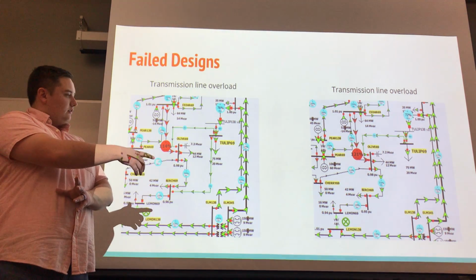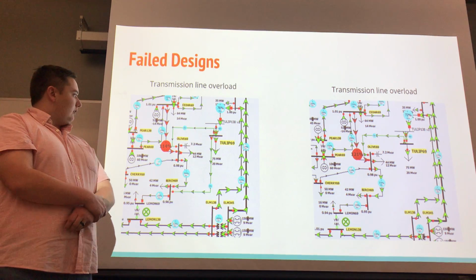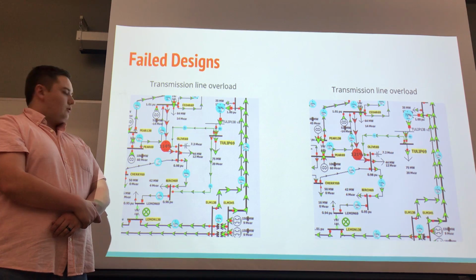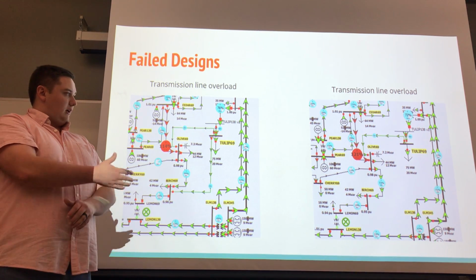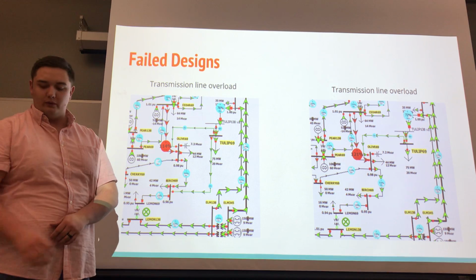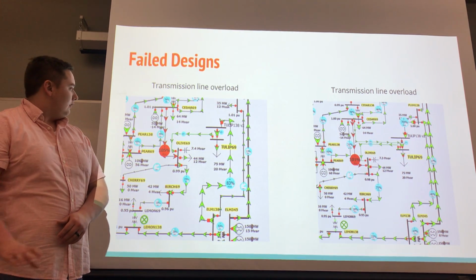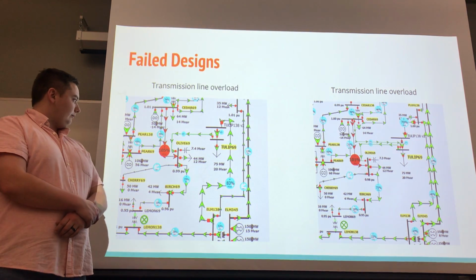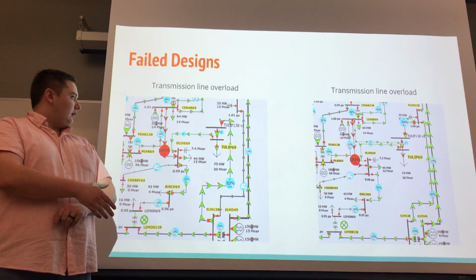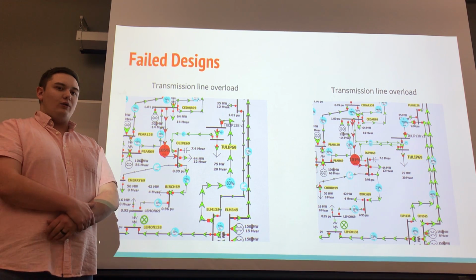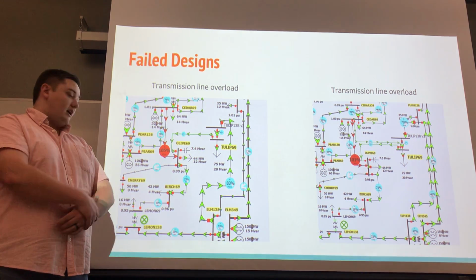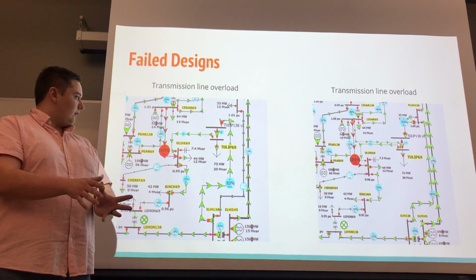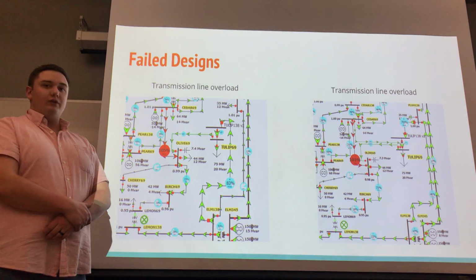And so for the next one, it was actually even more overloaded. And for that one, it's the same as this, other than that we took out the Tulip to Birch line, and that actually made the overload worse. So here you can see that the overloads are actually getting a little bit better with these new iterations. So this first one, we did Tulip to Olive and Tulip to Elm, and again, taking out the Lemon transformer was the biggest problem where we get our line faults from.